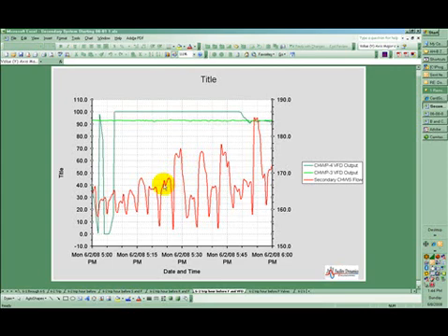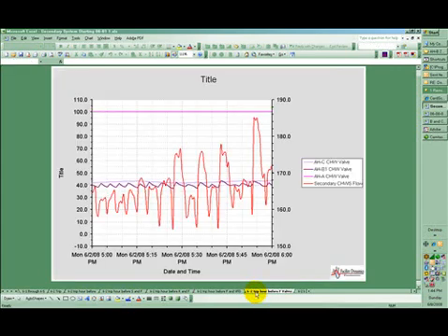So then I decided I'd look at what the valves in the system were doing, which is what this is. And if you look at this, what you can see is the A valve just flat out wide open, which is how it's been and actually still is, because we're trying to drive those basement zones down still. The C valve in this case was very flat. I mean, there's some waviness to that pattern, but nothing like Robert was seeing.